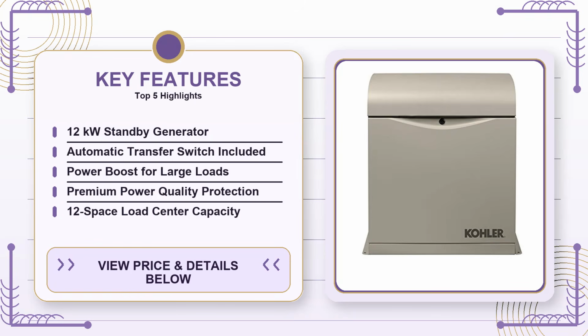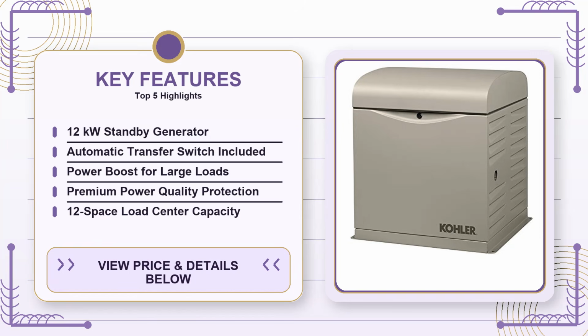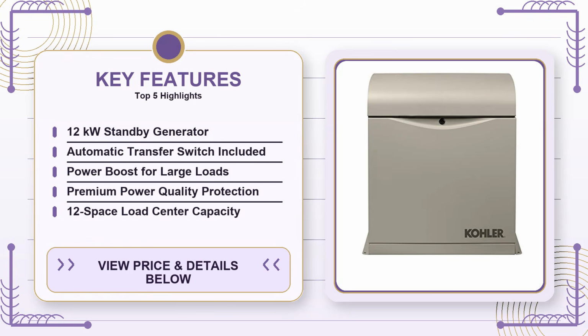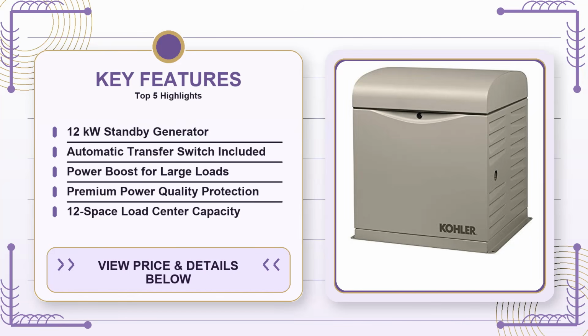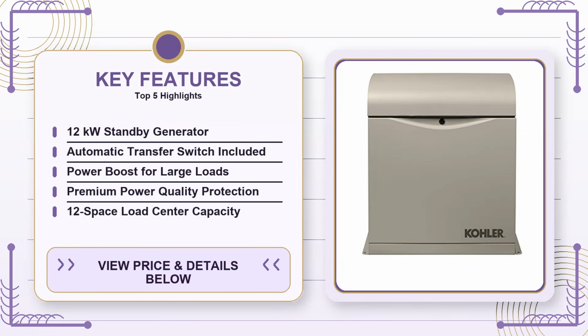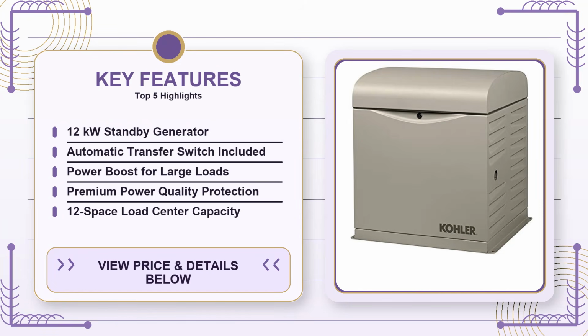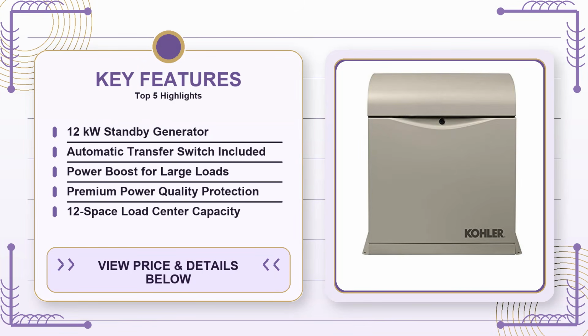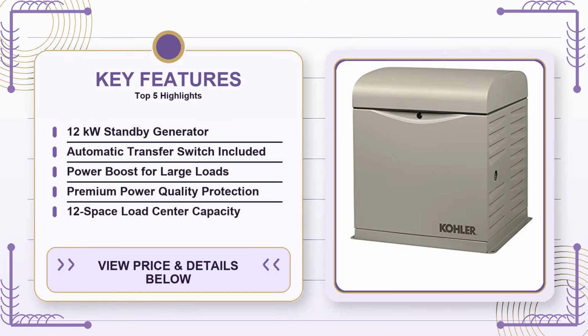On the flip side, if you live in a small apartment or a duplex where you only need to keep a few lights and a refrigerator running, you're likely overpaying for capacity you'll never use. A smaller, portable model with a manual transfer switch could give you the same essential backup for a fraction of the cost. Likewise, if you're on a tight budget and the idea of a professional installation feels like a barrier, this product might stretch your finances beyond the point of sensible ROI. The upfront cost includes the generator itself, the transfer switch, and the installation labor, often pushing the total into the high four-figure range.